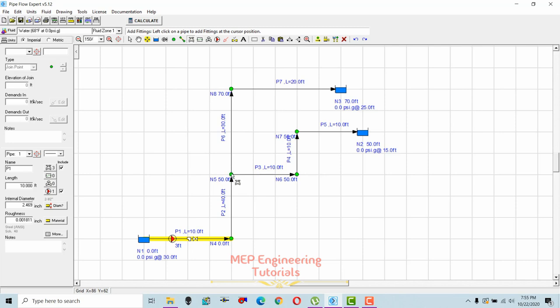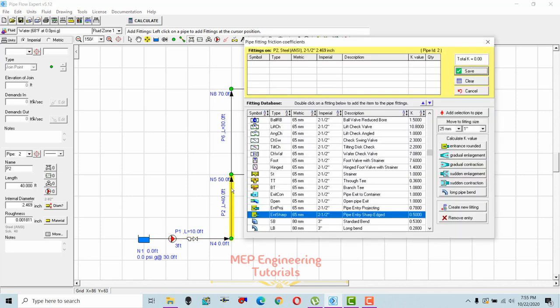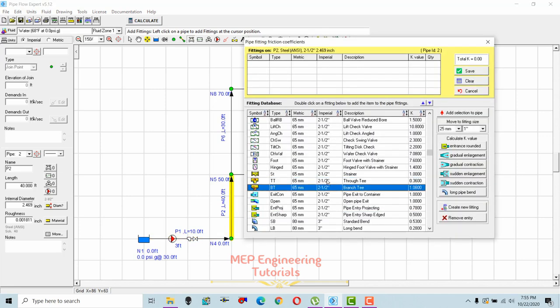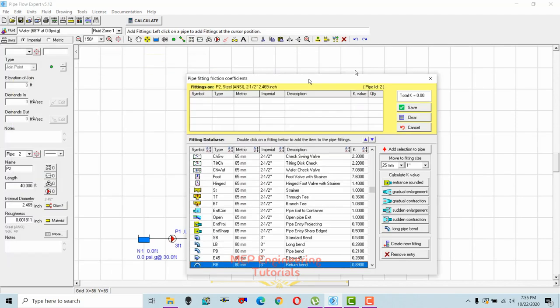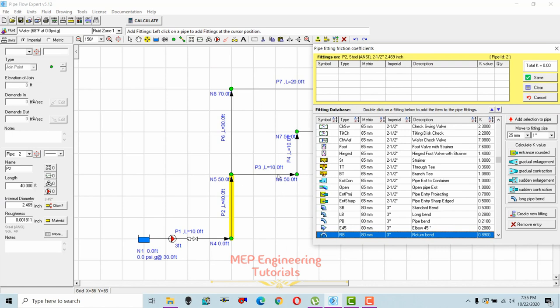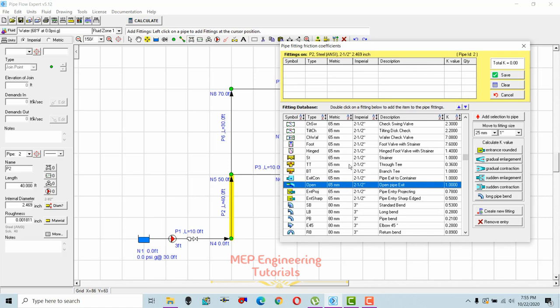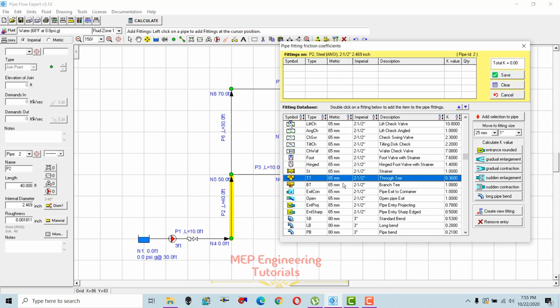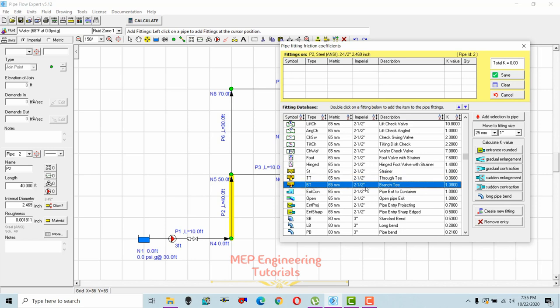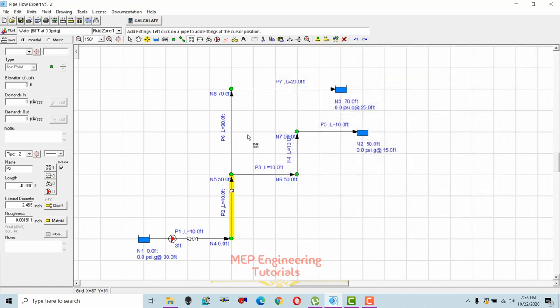At the tee connection point, I'll add a tee fitting. Select the pipe, go to Add Fittings, and select the 2.5-inch branch tee connection. There is a through-tee and a branch-tee option — I'll select the branch tee at 2.5 inches. The K-value is 1.08. Save it.